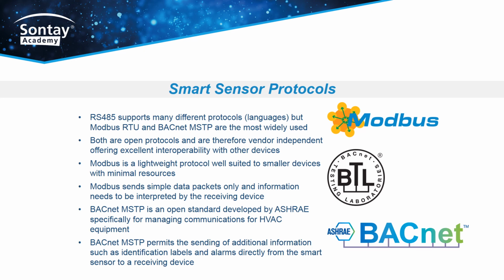BACnet MSTP is an open standard developed by ASHRAE specifically for managing communications for HVAC equipment. BACnet MSTP permits the sending of additional information such as identification labels and alarms directly from the smart sensor to a receiving device. RS485 is the physical network. In order to communicate between devices, it is necessary for all devices to be using the same protocol. Smart sensors will typically use one of two protocols, Modbus or BACnet MSTP.